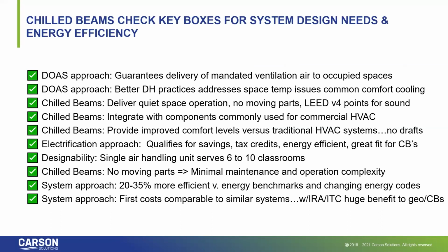So when you look at the system, it's not just the chill beam by itself, it is the system and the integration of these components. For example, DOAS delivers a known quantifiable amount of outside air, doing a better job of dehumidification, ensures better thermal comfort. Chill beams deliver quiet, comfortable operation within the space. If you pursue the electrification approach, chill beams are well suited and qualify for tax savings.